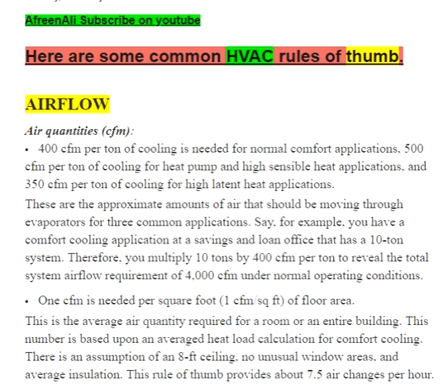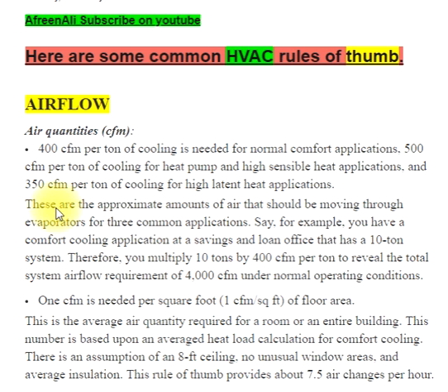Airflow Air Quantities CFM: 400 CFM per ton of cooling is needed for normal comfort applications, 500 CFM per ton of cooling for heat pump and high sensible heat applications, and 350 CFM per ton of cooling for high latent heat applications. These are the approximate amounts of air that should be moving through evaporators for three common applications.